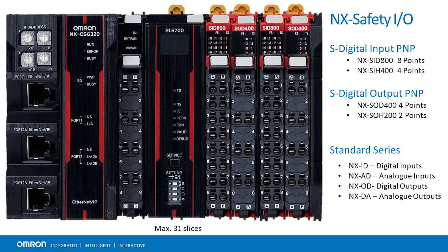For outputs, there are two options as well. The NX SOD 400 card offers 4 safety outputs with a maximum load of 0.5 amps per connection, while the NX SOH 200 offers 2 safety outputs with 2 amps per connection. The NX safety CPU unit and safety I/O units can be mixed with standard I/O units to create a complete modular safety control system. There are over 100 types of standard NX I/O units available, including digital and analog I/O units, temperature input units, and encoder positioning units.